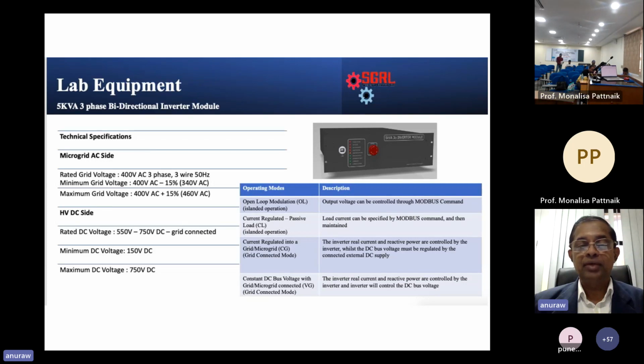Otherwise your reverse power flow might flow to the grid and put servicemen in trouble, so that is not permitted. There are various protection devices, such as loss of mains and others, which protect the solar system from feeding into the grid during an outage, while it continues to supply the house.